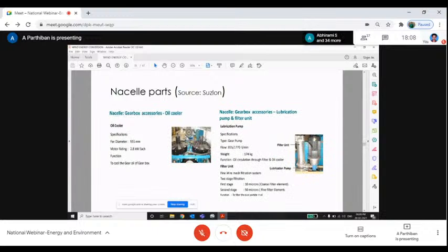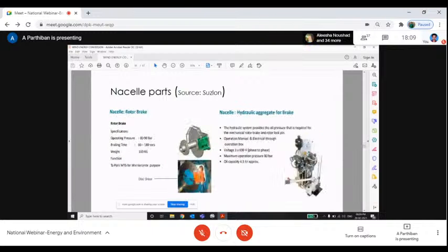These are some accessories: oil cooler, lubrication system, and filter unit. In the gearbox there is oil which should not go beyond a certain temperature limit. So to maintain the temperature limit, the oil cooler is used. And these are the hydraulic units and mechanical brakes. When we want to enter the hub, we need a brake, because it should not start rotating. So to stop the rotation, so that manpower can work in the hub for maintenance activities or for attending a breakdown, we have a brake system.